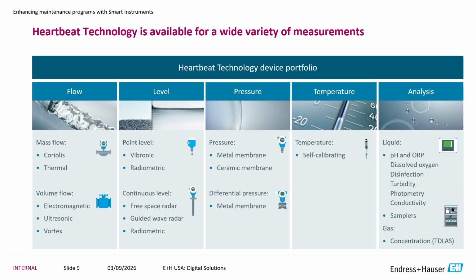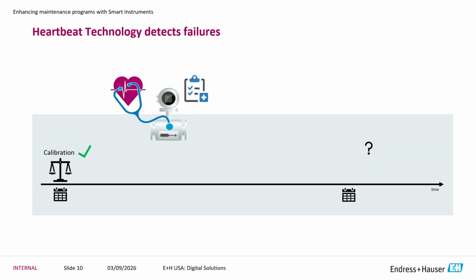There are also several other technologies we offer this verification for—level, pressure, temperature, our liquid analysis line. Coriolis tends to be the one everybody goes to because they really don't want to calibrate them, and we know it's not always a true functioning measurement, so we're not controlling a whole lot off Coriolis. It's an easy one to pick off first. But we have this technology throughout our entire instrumentation portfolio.